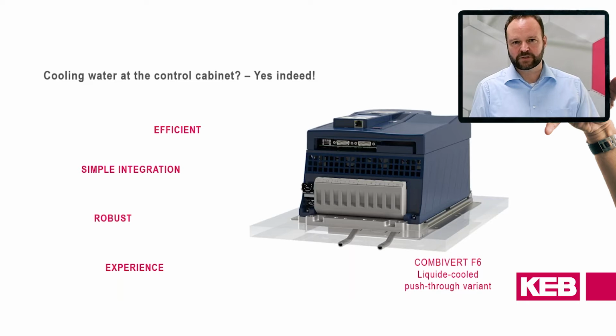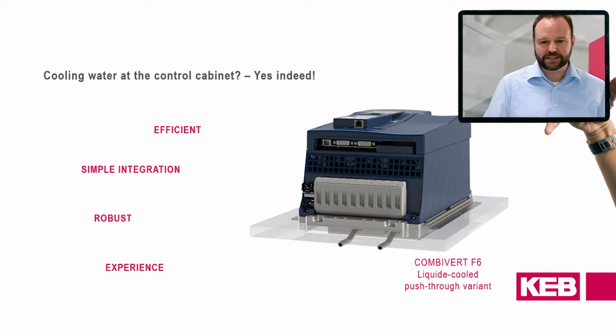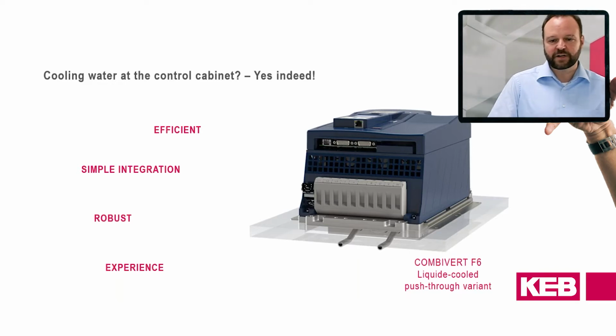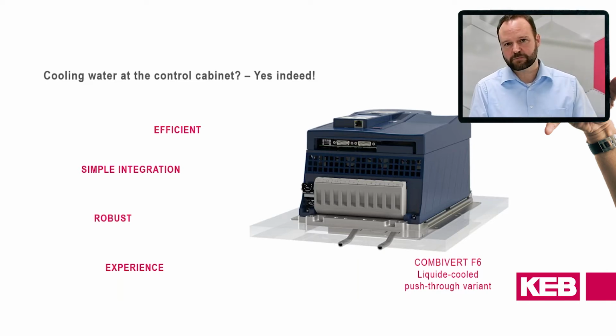Also, we use stainless steel tubes for the water. This makes it robust against corrosion or pitting and increases the availability of the drives, or at the end, of course, the availability of your machine. Optionally, we offer built-on braking resistors on the drive, on the water-cooled heatsink. This saves wiring costs and is very efficient and space-saving at the end.